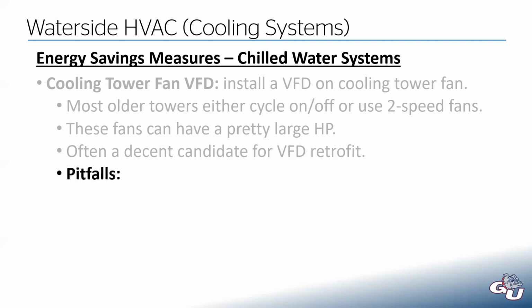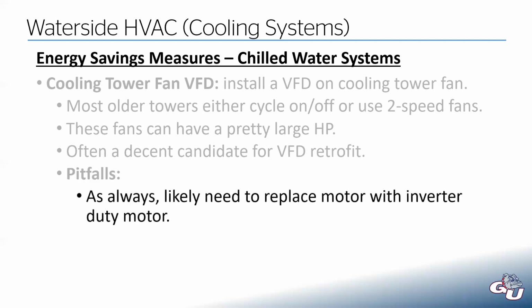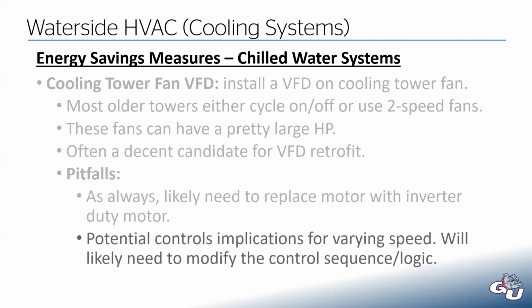The things to watch out for: you do need to replace the motor with an inverter duty motor, because that's true of any VFD retrofit. And you're going to have some potential controls implications for varying that speed. You'll need to have a control system that knows how to ramp the fan speed up and down.